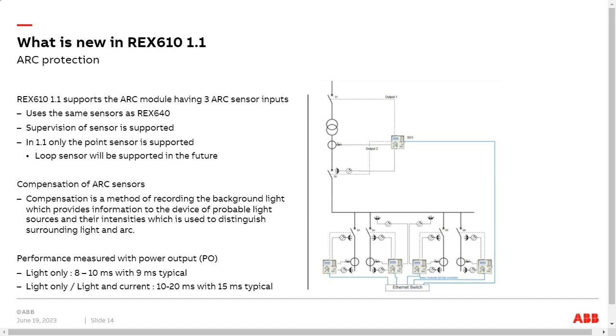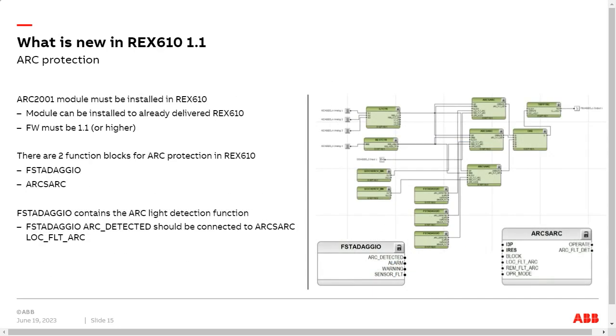Now, looking a little bit more, to be able to use this arc protection, you need to have the so-called ARC 2001 module in the 610. This module can of course be ordered directly from the factory and installed in a device, or you can even order it loose. For example, if you have a REX610 device on your desk, you can order the ARC module from the factory, and then add it to this device.